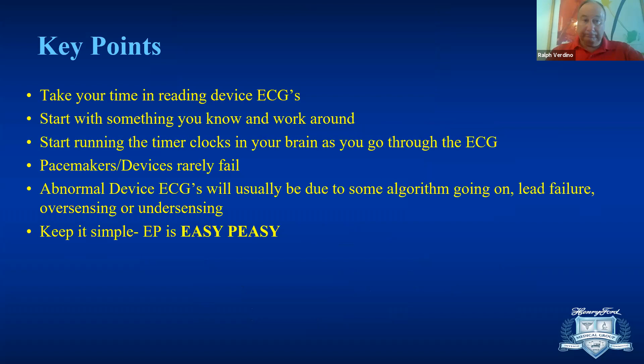So let's start. Just the key points, whenever I teach fellows: keep things easy, right? Take your time in reading device ECGs. Read them the way you do any other ECG, from one side to the other side. Start with something which you know, so find a pace beat and then work around. The moment you see a device ECG, the timer's clock should run in your brain as well, just the way it runs in the pacemaker. So the AV delay timers and the PVARP, those are the main ones which should keep running in your brain to figure out what pacing spike is going where.